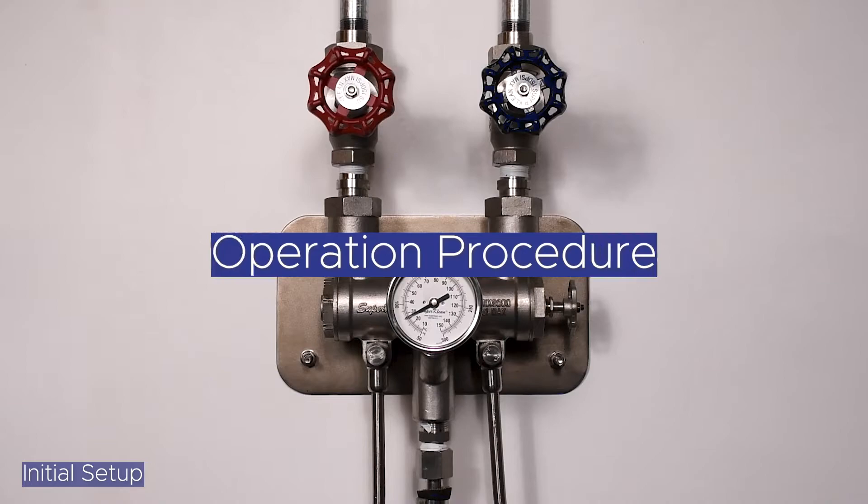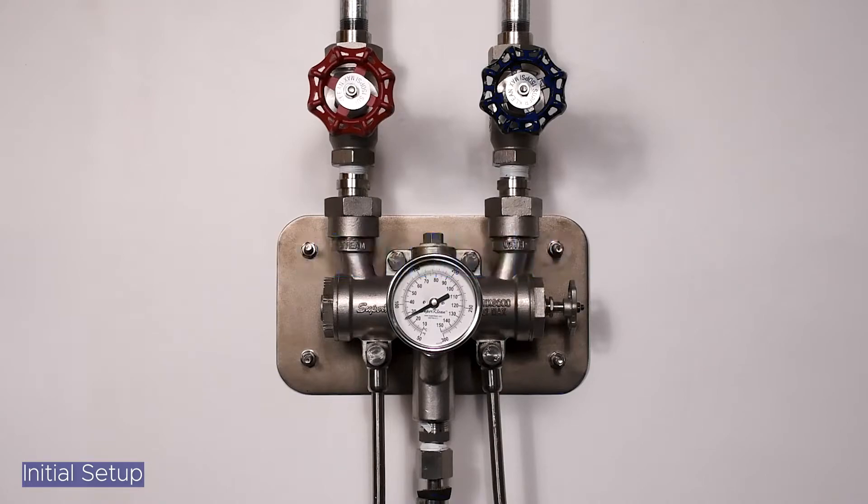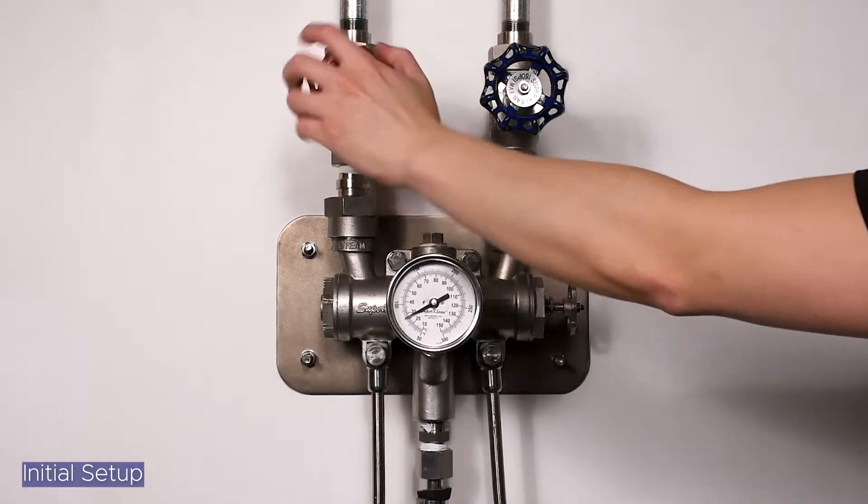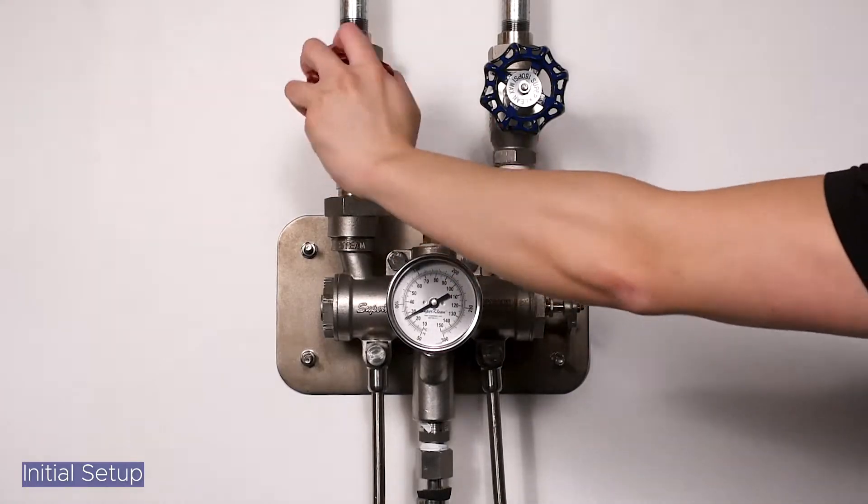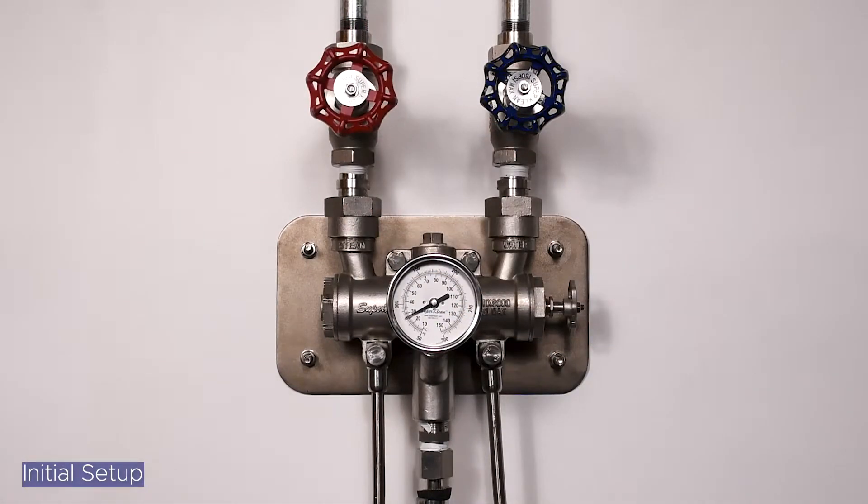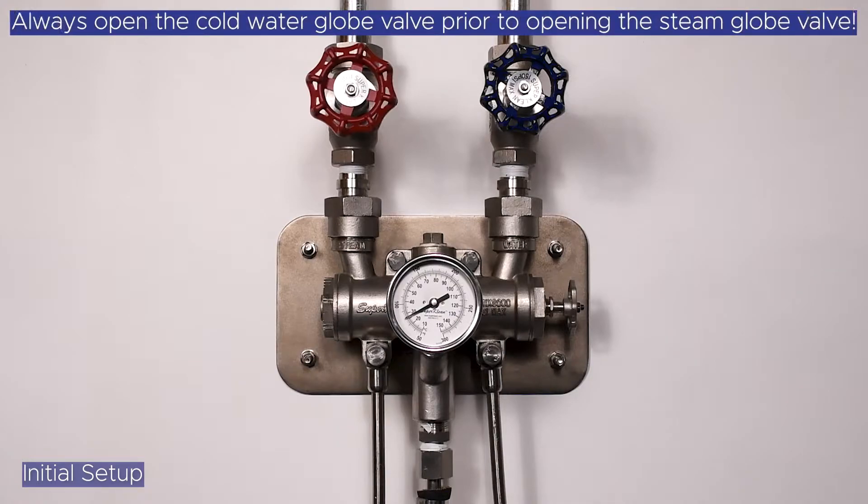To set your desired temperature for the first time and to begin operation, open the cold water globe valve to its full open position by turning the blue globe valve counterclockwise. Next, open the steam globe valve to its full open position by turning the red globe valve counterclockwise. Always open the cold water globe valve before opening the steam globe valve.